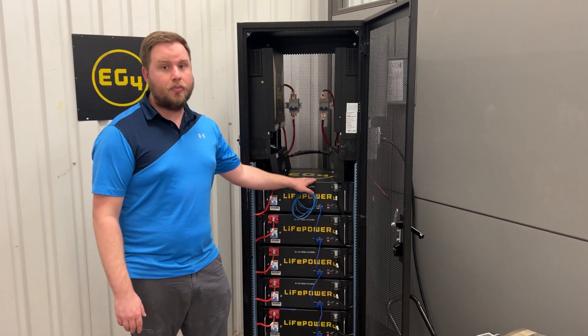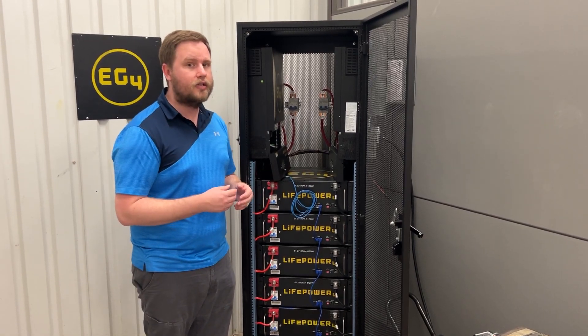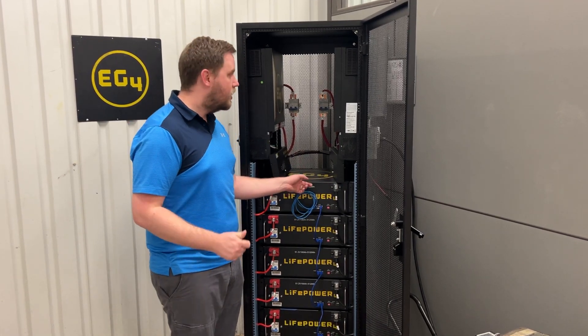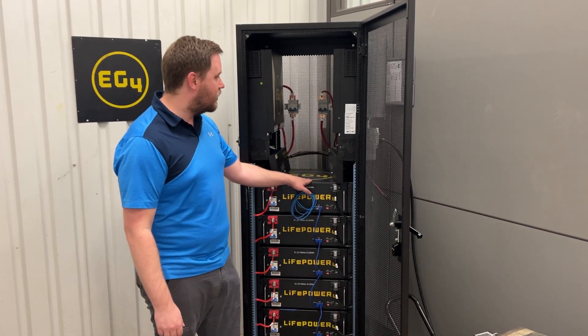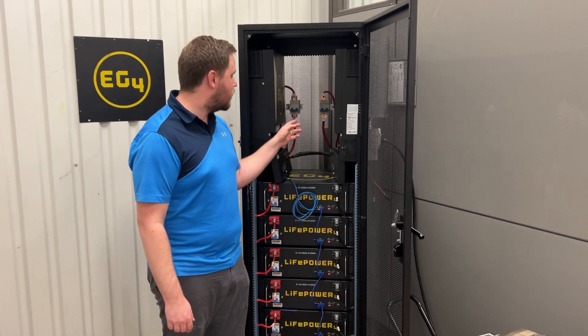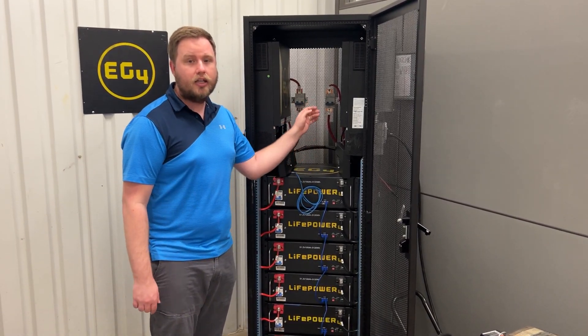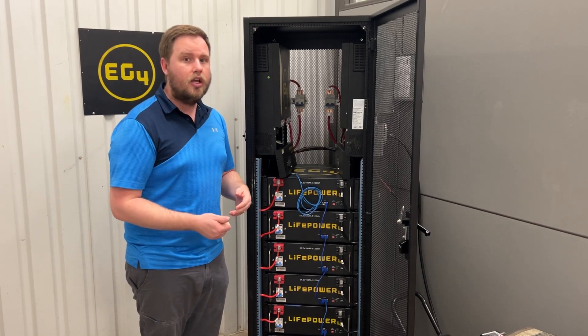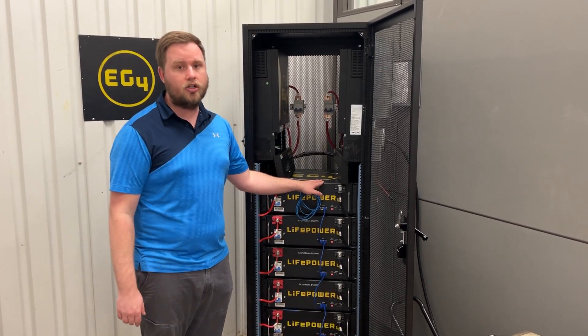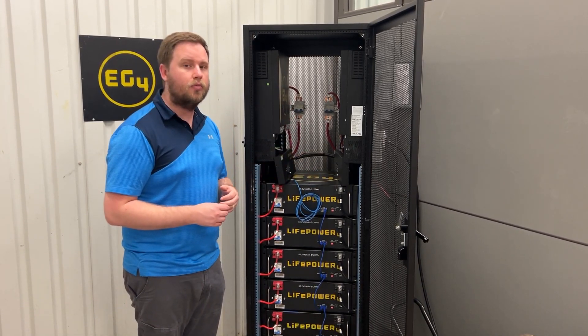The LifePower4 has a built-in pre-charge resistor, and you can actually hear it when it's operating during the initial startup process. It kind of sounds like a clicking noise. When you're starting these up, they need to have an open electrical connection to the inverter. By that, I mean the breakers or anything you have inside there need to be in the on position. If you have them flipped into the off position, it's going to go through its pre-charge cycle but it's not going to actually do anything to start the inverter with the pre-charge.